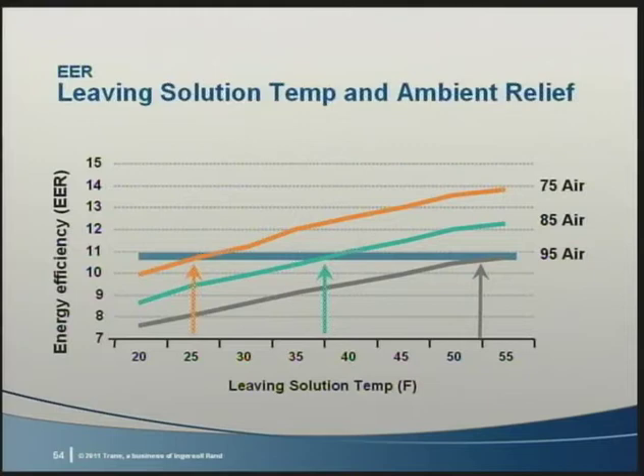But just like with the kW per ton versus kW, the EER doesn't tell the whole story, because the size of the chiller needed in an ice storage system affects the full load kW, and in the case of partial storage, there are more run hours on the ice storage chiller. We have to go to kW to find out what will be setting our on-peak demand charge and to kilowatt hours to compare actual energy use.